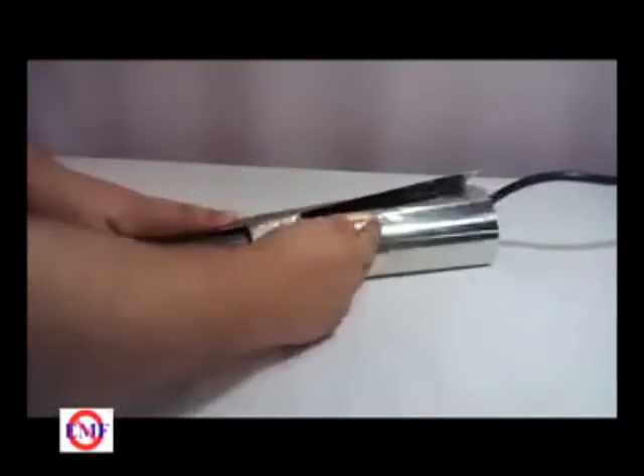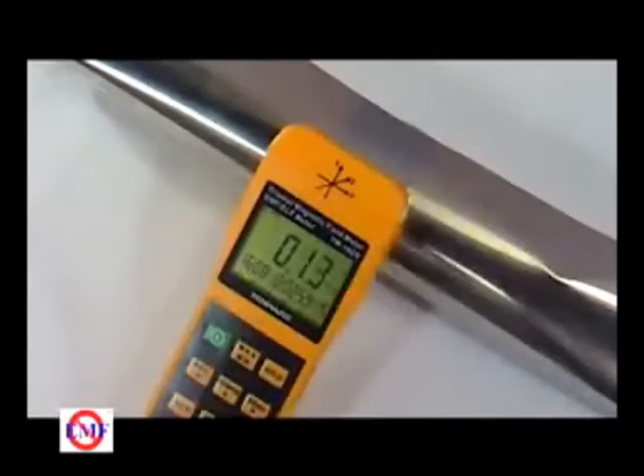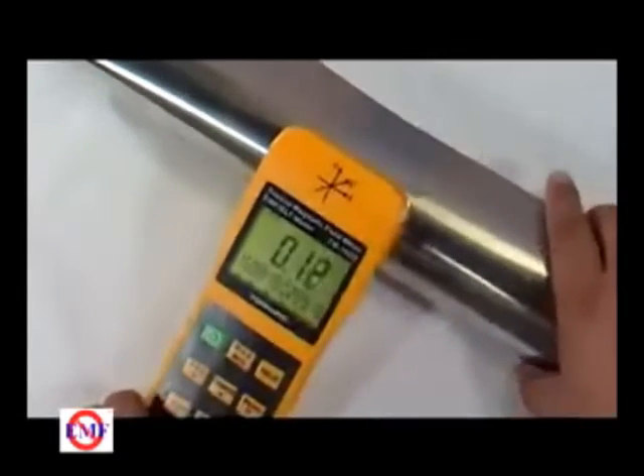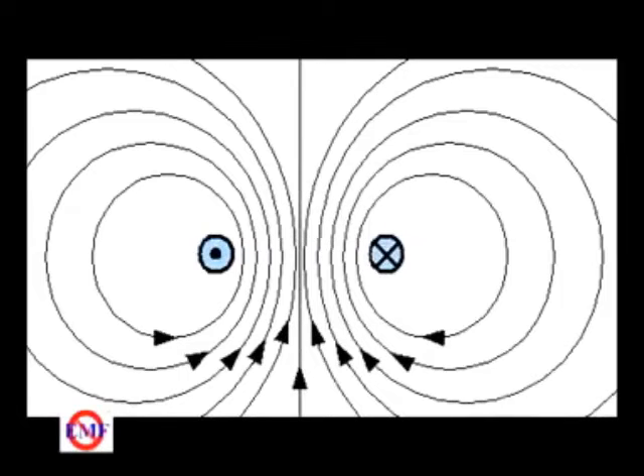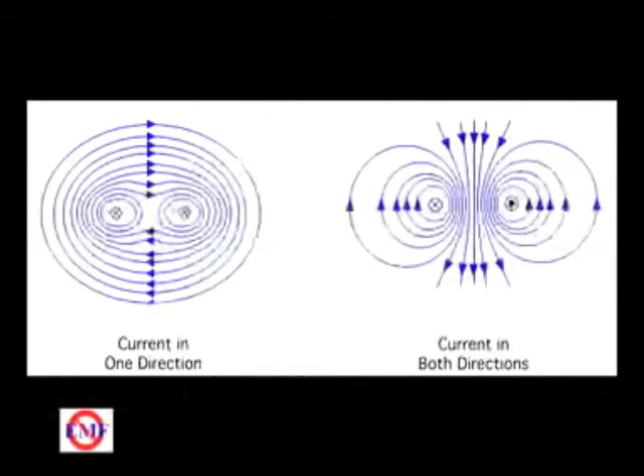Shielding magnetic fields from balanced current is done by wrapping the wires with magnetic shielding foil. In this situation, some of the magnetic field is actually cancelled out due to the equal currents moving in opposite directions. The remaining field is no longer in the shape of concentric cylinders around the wire, resulting in higher efficiency when wrapping the wire.